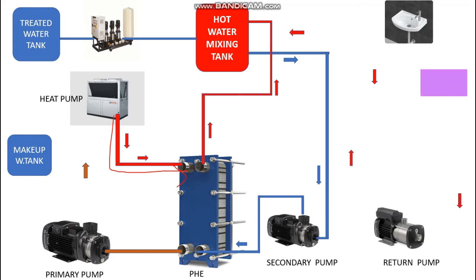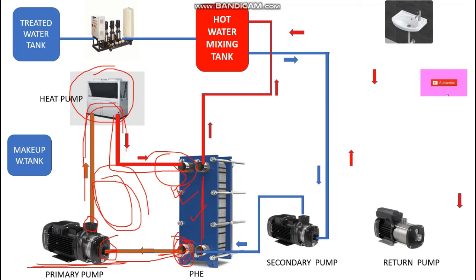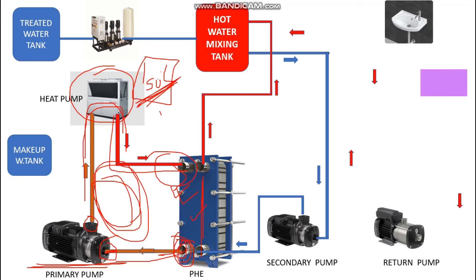The hot water that entered from the heat pump outlet has given its heat to the cold water, so the temperature of this water at the leaving side of the PHE decreases. It then connects to the suction of the primary pump. The primary pump takes this water from the outlet of the PHE and feeds it back to the heat pump to make it hot again. The heat pump maintains this water temperature up to the temperature setting — for example, 50°C. The cycle repeats until 50°C is reached, at which point the compressor goes into rest condition.